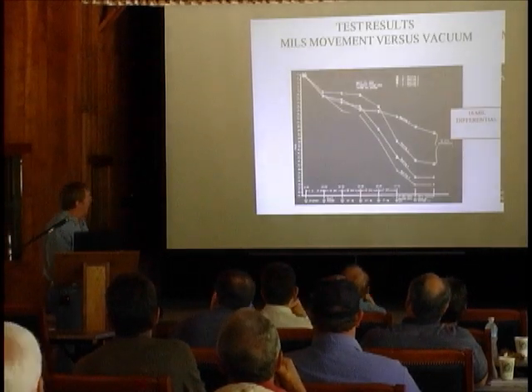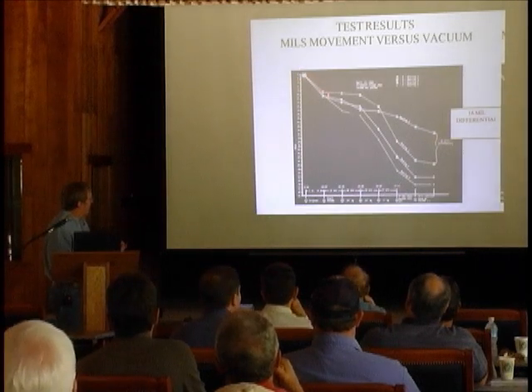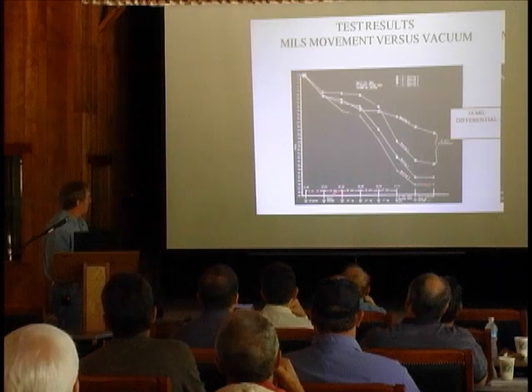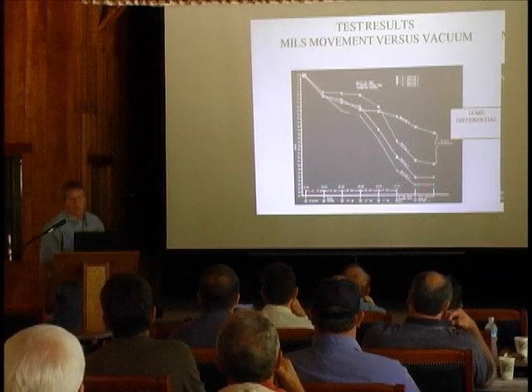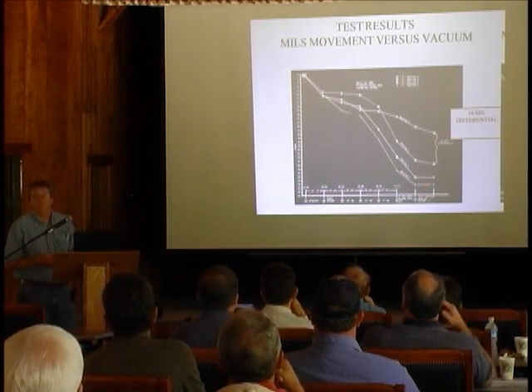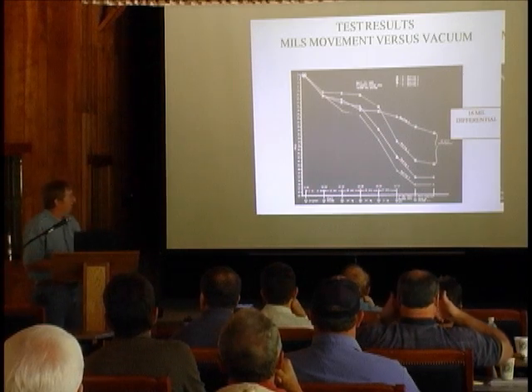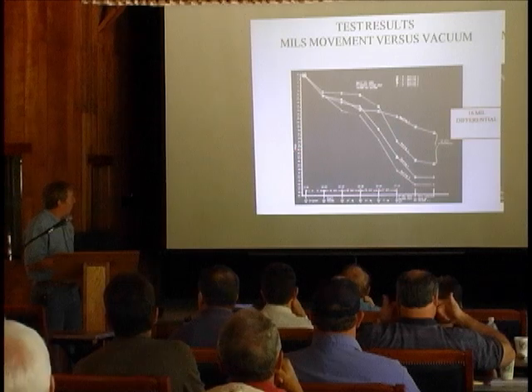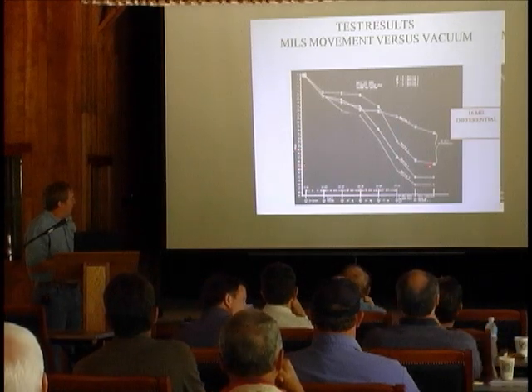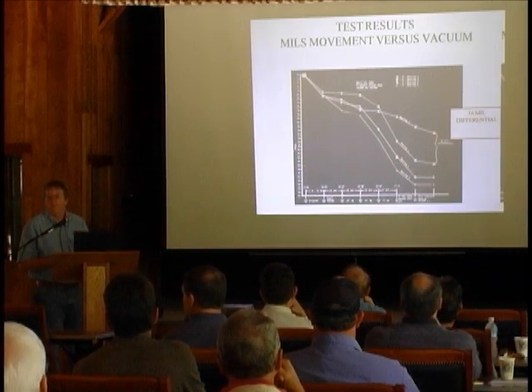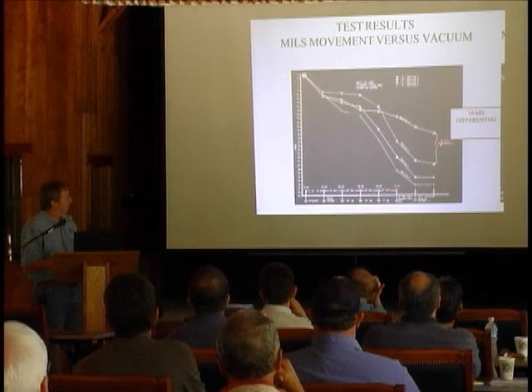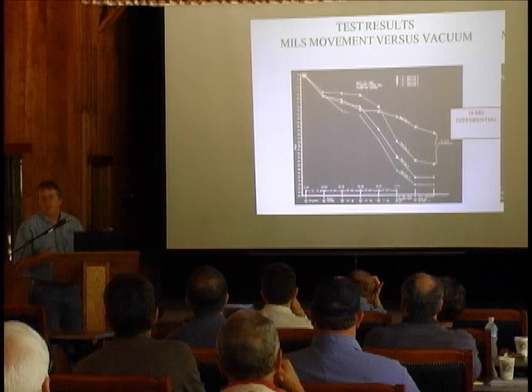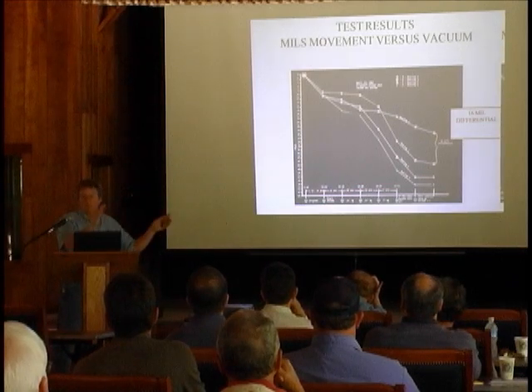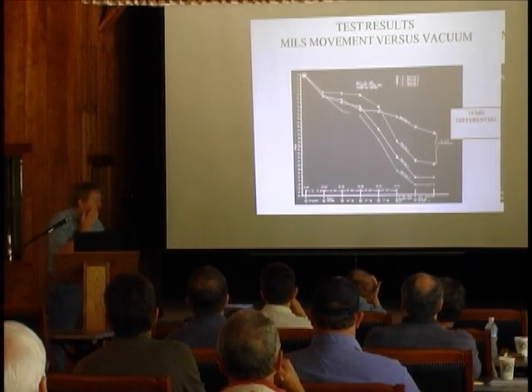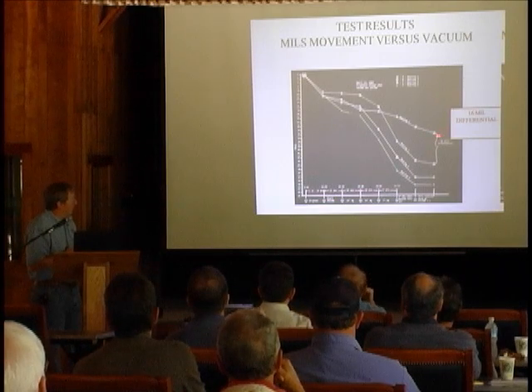So anyway, I did that, and we drew vacuum, and wow, when you draw a vacuum on a big turbine, they move a lot. That's what we found out. And that's okay, I don't care as long as the whole turbine drops, but the problem is one bearing dropped more than the other. It dropped 16 thousandths more. In other words, the bearing that was going into whirl dropped 16 thousandths more than the high pressure bearing, which doesn't sit on the condenser. So that was one factor.